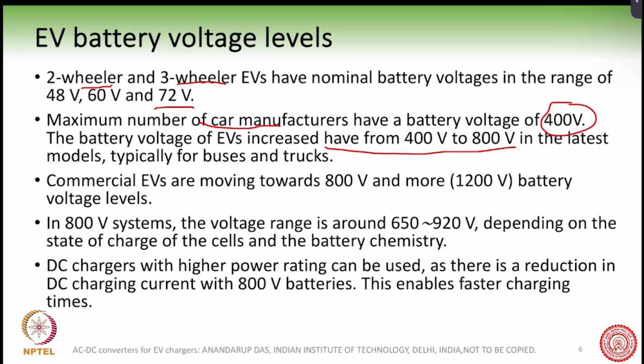As we go into higher voltage, for the same power, the current reduces, and therefore the conductor dimension reduces. So if you go from 400 to 800 volt, it is expected that the conductor size reduction will be possible.